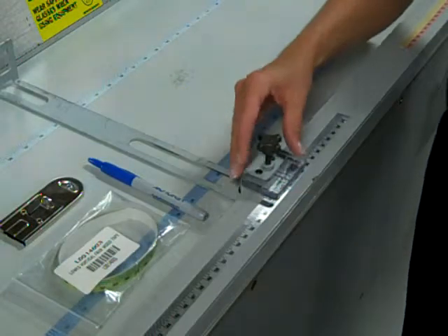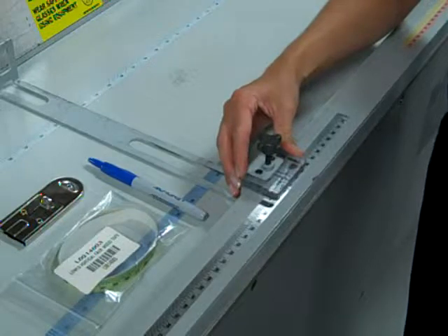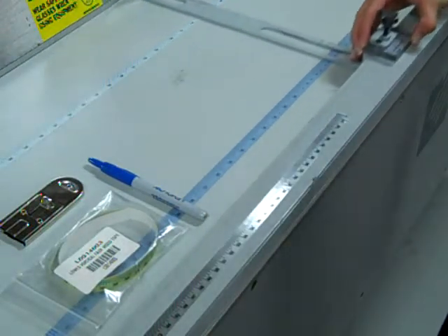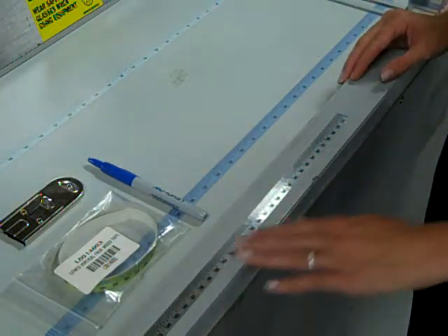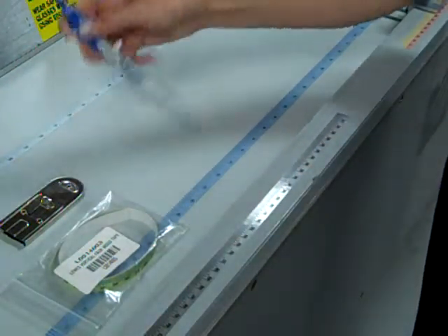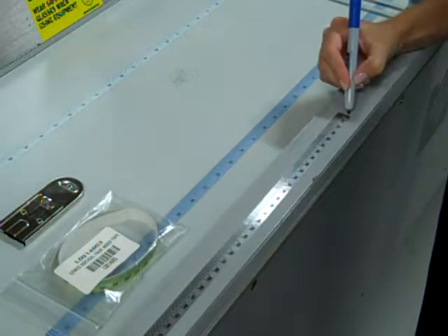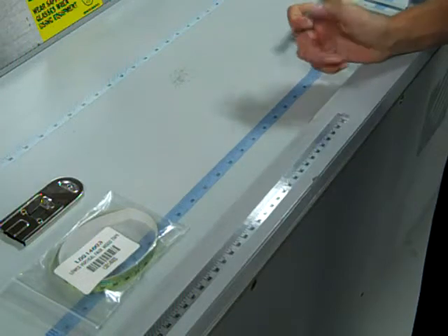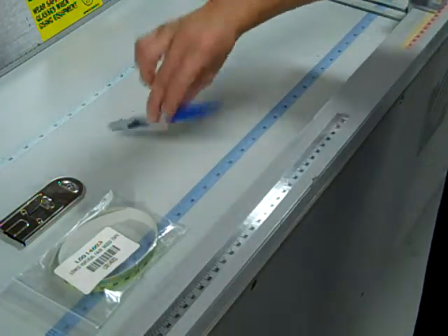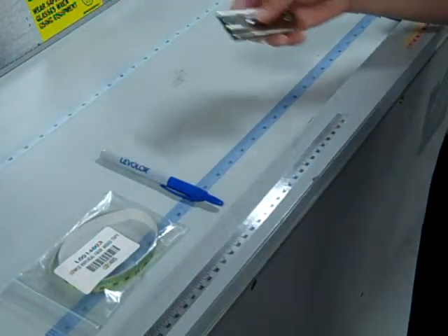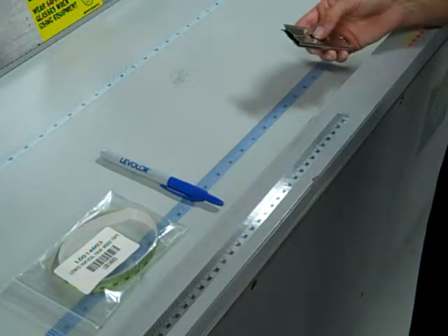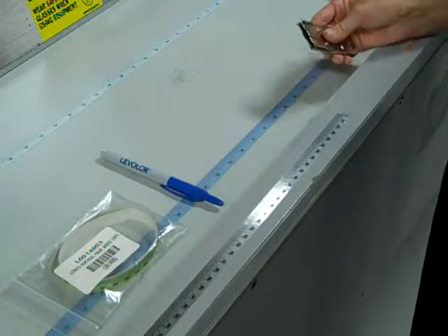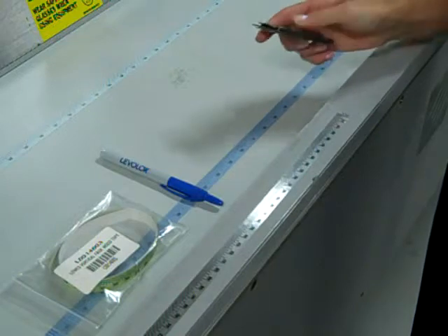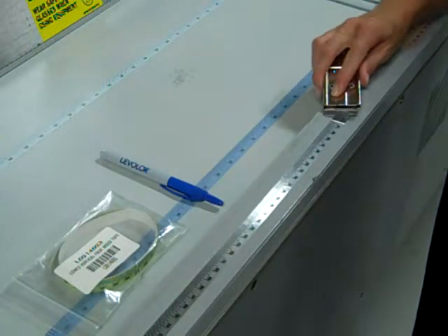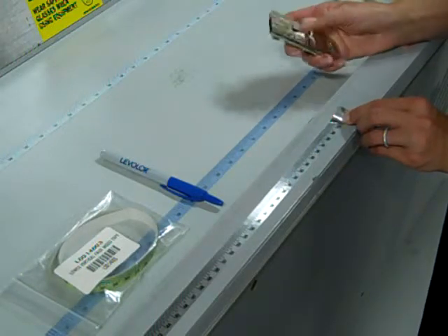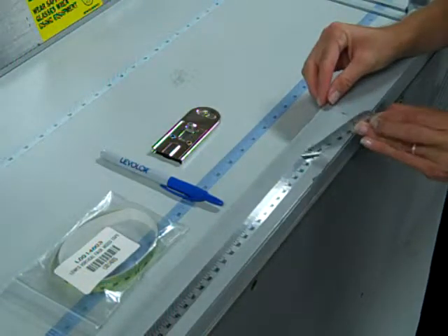To remove the tape during the calibration process, the first thing that you will need to do is slide the center measuring guide down to the right of the machine so it gets out of the way for the removal process. Next, you will take your Sharpie marker and make a small mark along the right edge of the current tape to mark the current tape location. This way you understand which way to relay the tape or replace the tape to the left or to the right of that initial or current mark. Next, you will take your tape scraper and gently slide it underneath the edge of the machine tape that you need to remove. From here, you can easily peel up this tape for replacement.